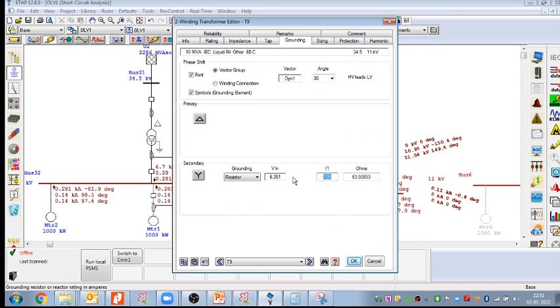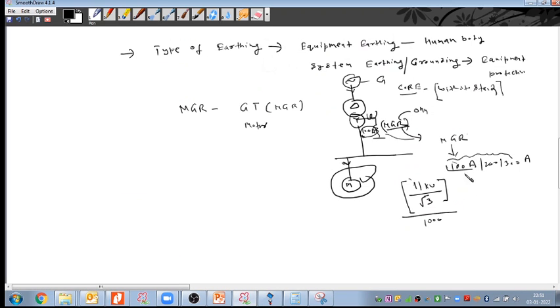But if I change my current to 50, then this will be 120 right now. If I change it to 200, then it will be 31. So first of all, we should know how much current we want to allow to flow through the NGR. Based on that, we decide the impedance of the NGR, our neutral ground resistor rating. Hope this point is clear, this is what we discussed.